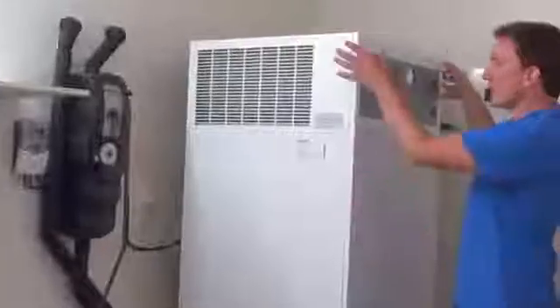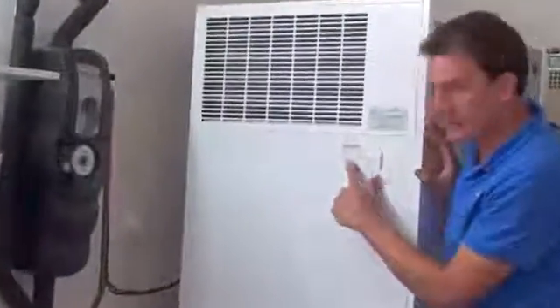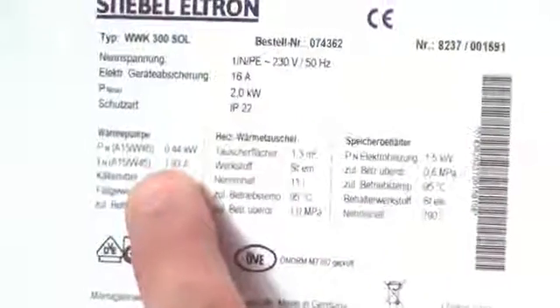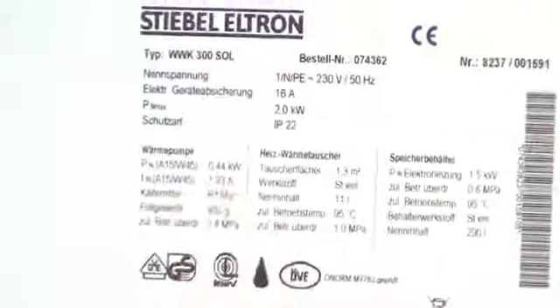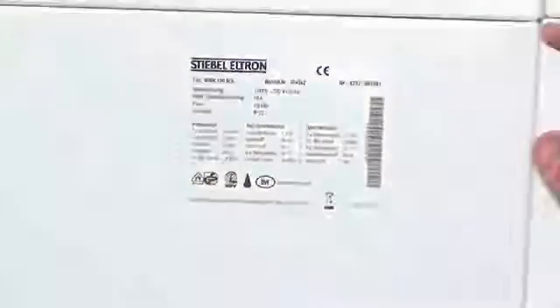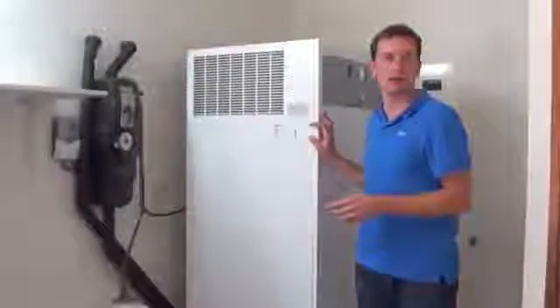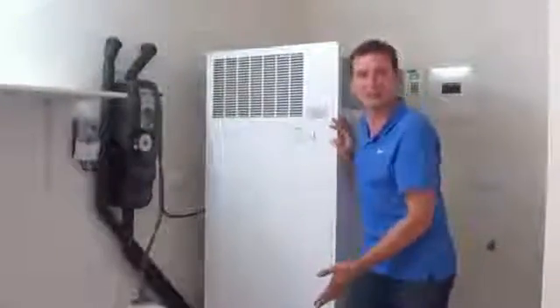To give an idea of how efficient a heat pump system is when you combine it in an integral unit, if you can have a look here on this side, this heat pump consumes 0.4 kilowatt to heat up 300 litres of hot water. Now that on its own is amazing. If you're not very technical, to give you an idea, 0.4 kilowatt would be the same as 4 light globes in your house to heat up 300 litres of water.